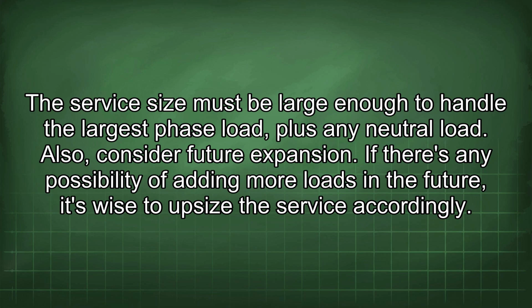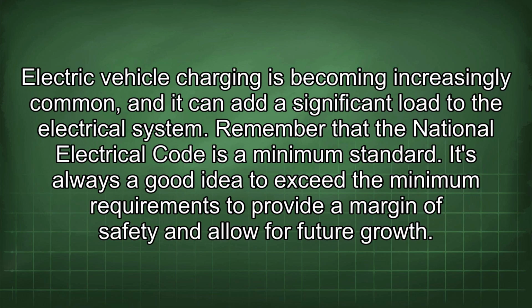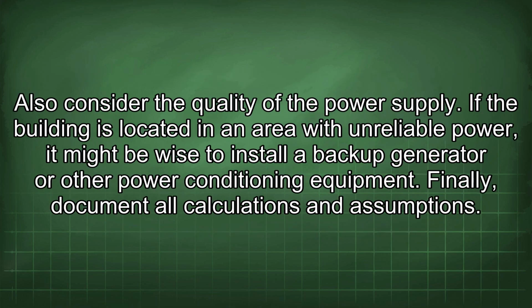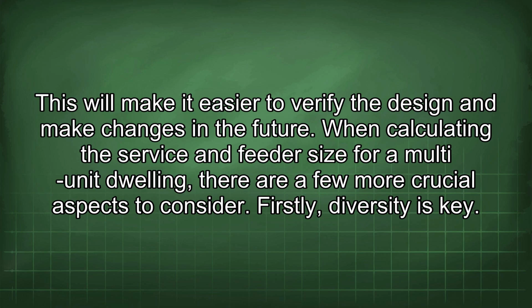Also, consider future expansion. If there's any possibility of adding more loads in the future, it's wise to upsize the service accordingly. Electric vehicle charging is becoming increasingly common, and it can add a significant load to the electrical system. Remember that the National Electrical Code is a minimum standard. It's always a good idea to exceed the minimum requirements to provide a margin of safety and allow for future growth. Also consider the quality of the power supply. If the building is located in an area with unreliable power, it might be wise to install a backup generator or other power conditioning equipment. Finally, document all calculations and assumptions. This will make it easier to verify the design and make changes in the future.